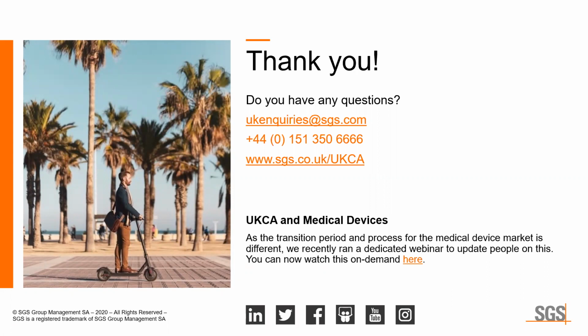Is there any requirement regarding the UK importer's address? We've heard that this address can actually be mentioned on any document accompanying the product. Could you confirm, please? Again, the law states that the address should appear on the product if possible. Much like the CE mark, the address should appear ideally on the product itself. Again, if size or shape dictates it's impossible to do so, then the address can be put on accompanying documentation or packaging, but it should appear on the product.